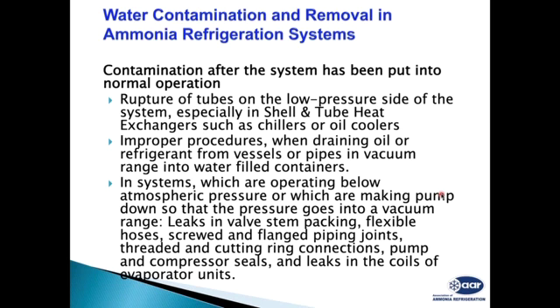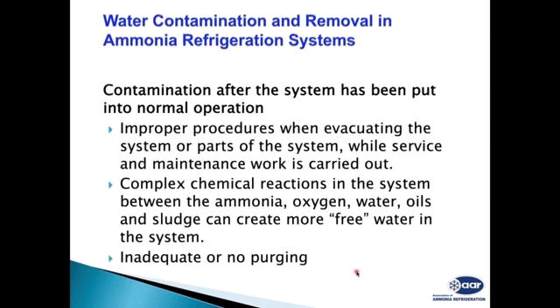Then there is a possibility of rupture of tubes, like on the condenser side or the receiver side, shell and tube, ice bank tanks, chillers. We have these systems where water and ammonia can come into contact. If there are any ruptures or leakages, water will enter. Sometimes while draining oil or refrigerant from the system, there are possibilities of water entering. Also, when the system is operating below atmospheric pressure, during pump down, leakages in valve stems, hoses or flange joints will allow air to enter, and along with the air, water will enter.